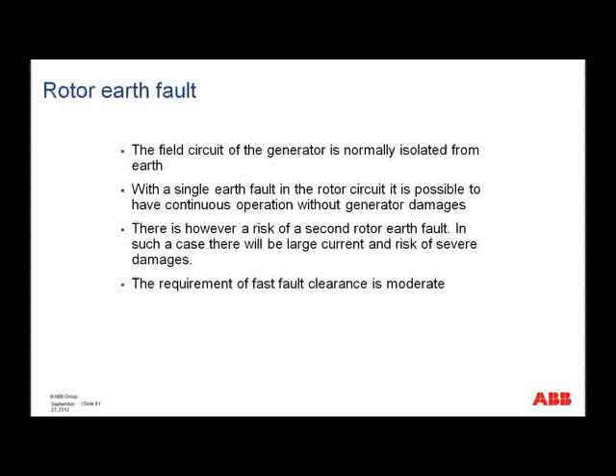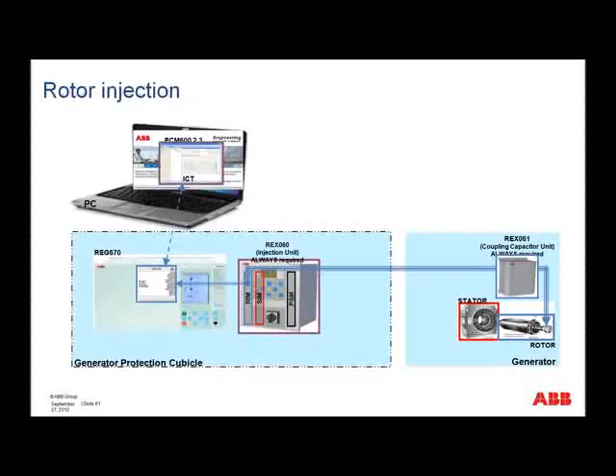Right, rotor earth fault. The field circuit of the generator is normally isolated from earth. With a single earth fault in the rotor circuit, is it possible to have continuous operation? Because the rotor is normally isolated from earth. But of course, the problem is what happens if we should get a second one, and then you could have large current and risk of severe damage. So the requirement for fast clearance is moderate. Just because we have one doesn't mean the next one would come immediately, but it's something that you would not want to ignore.